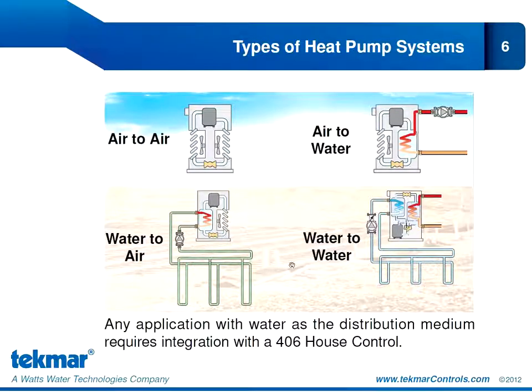Now, why does all of this matter? Well, it matters for 2 reasons. It matters for proper control selection and also to properly configure the settings in the 557. The 557 was designed to operate heat pumps that use air to distribute the energy to the building. Any application that's using water as a distribution medium requires that the 557 be paired with the 406 house control. And in this webinar presentation, we're going to see how the capabilities of the 557 really complement the functions of the 406 house control.